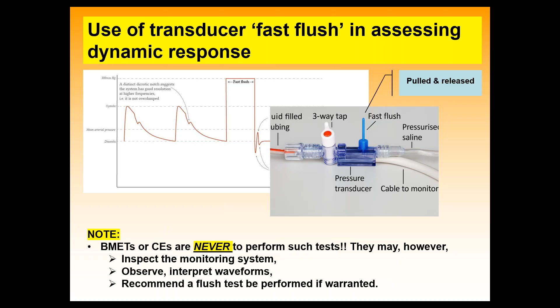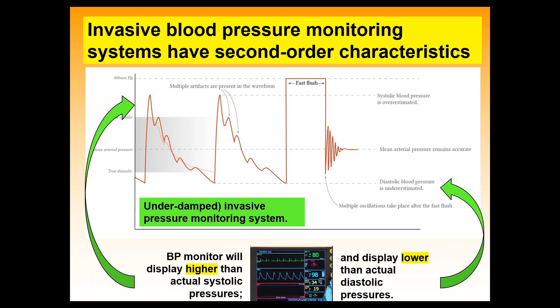Okay, if it was underdamped, you're going to see all kinds of artifact where the dicrotic notch should be, because there's only one of them, not a bunch of garbage in there, and you'll see a lot of ringing, classic ringing here. It's a hallmark of an underdamped system. Again, that's the car with the bad shocks oscillating that way. In the classic tip-offs, the much narrower systolic peaks are going to be overestimated, and the monitor will display larger systolic pressures than it should. The dicrotic notch will be exaggerated, but the mean is still the same. So the mean is relatively immune from these resonance issues.